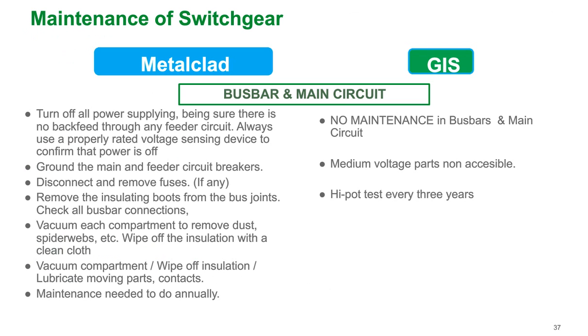So, maintenance of the switchgear. I'll go through these pretty quickly because there's a lot of detail on these slides. You can refer to it later. But the main thing, comparing maintenance procedures, GIS versus metal-clad, you've got essentially no maintenance on the bus bar, no maintenance on the main circuit. Medium voltage parts aren't accessible, whereas on metal-clad, you typically have to inspect the circuit breaker, withdraw it, test BIL. You have to lubricate the mechanism every year.